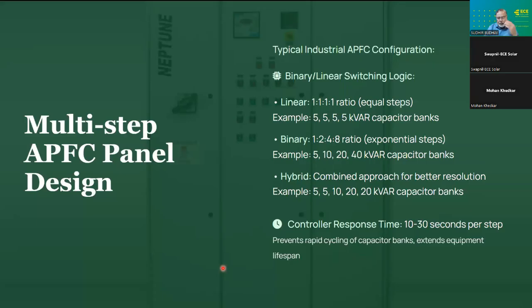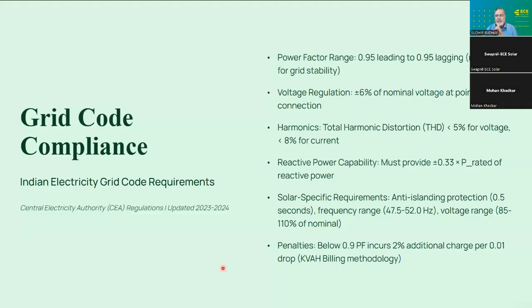Now, let's go ahead with grid code compliances. Now, Central Electricity Authority has certain regulations where we have to follow grid code, and power factor range is 0.95 leading to 0.95 lagging. Then voltage regulation is plus minus 6% at the point of connection. Then harmonics should be less than 5% for voltage and less than 8% for current.